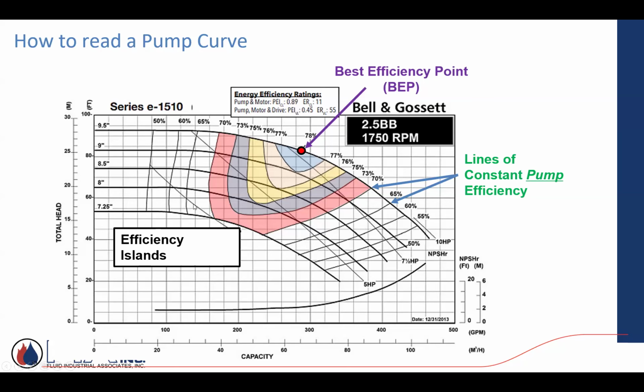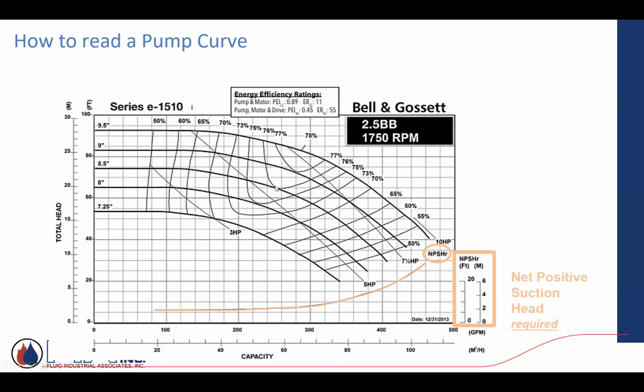And as you increase or decrease the impeller diameter, you move closer or further away from those efficiency curves. Down here on the bottom right, there's a curve that sits off to the right and it says NPSHR, net positive suction head required. This is established by the pump manufacturer. He says, I need to have this much static positive pressure of water in the pump so that I don't cavitate. So there's two NPSH numbers.